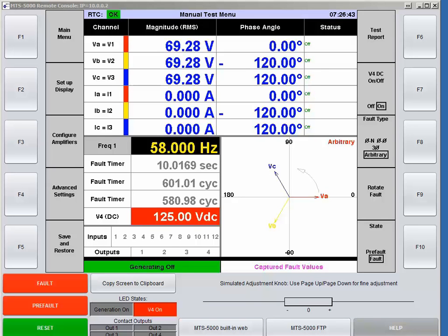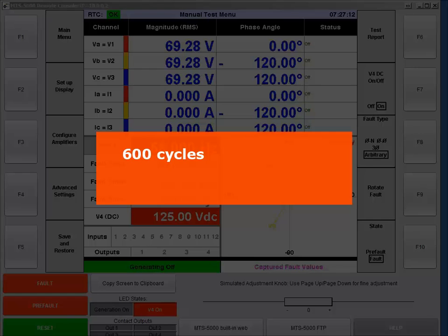However, these relays use different references for the time delay in cycles, so they will have different time delays. The SEL relay will use the injected frequency, which means the actual time delay in seconds will vary depending on what frequency is being injected at that moment. The Beckwith relay will operate in 10 seconds every time, because the 600-cycle delay is based on the system frequency — in my case 60 Hz — so 600 cycles divided by 60 Hz equals 10 seconds.